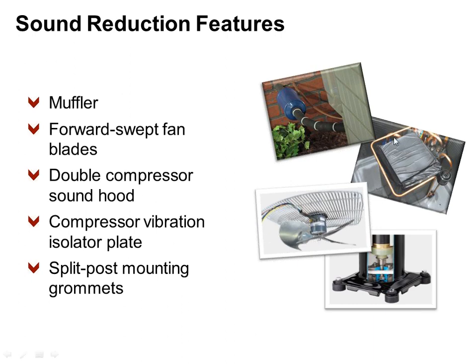This guy has 2 sound compressor blankets on him, right? So there's a square one on top, and then there's a traditional round one on top of him underneath that. It has vibration isolators. So if you can see in the bottom right, it has all these grommets here that it's posted on. So the 4 ends of the compressor are posted on a rubber grommet that isolates the sound, and that's mounted to a laminated plate instead of a regular sheet metal plate. So lots of things that go into this guy to make him a little bit quieter than the average unit.